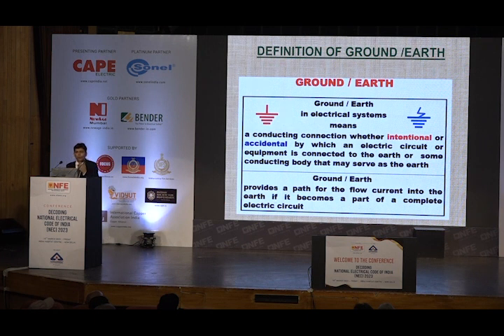Definition of ground or earth: a conducting connection, whether intentional or accidental, by which electric circuits or equipment are connected to Mother Earth or to some conducting body that may serve as earth or ground. It provides a path for the flow of electrical current back to the source, a dedicated path for that short circuit current to go back to the source.